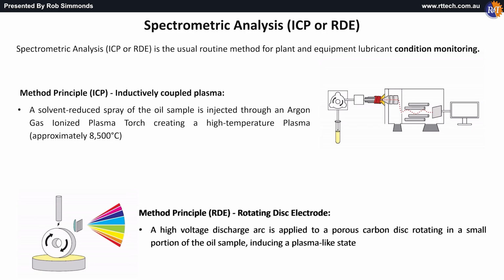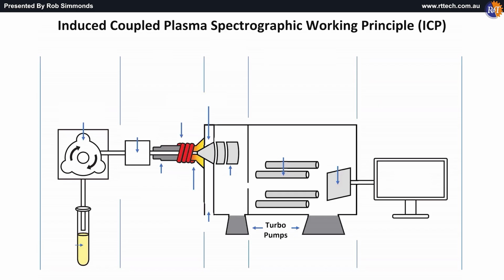Method principle RDE, rotating disc electrode. A high-voltage discharge arc is applied to a porous carbon disc rotating in a small portion of the oil sample, inducing a plasma-like state.